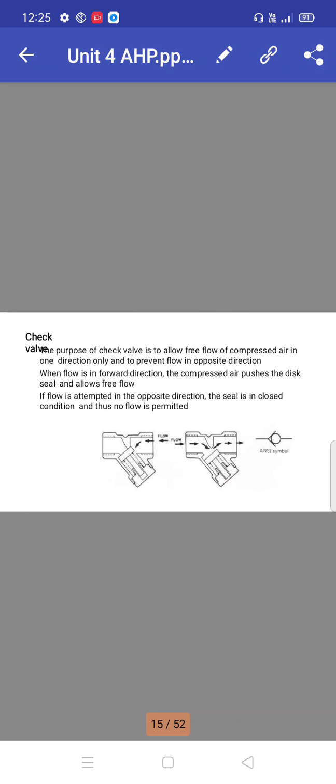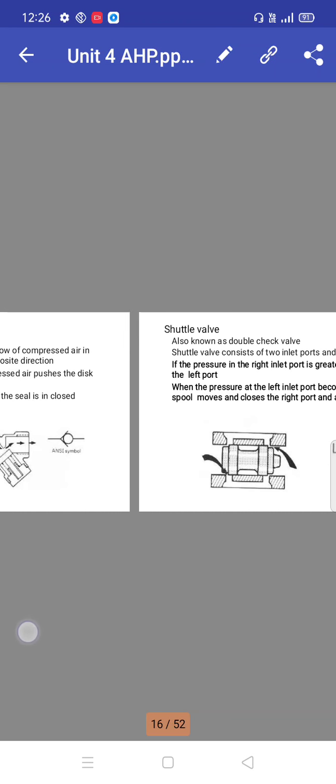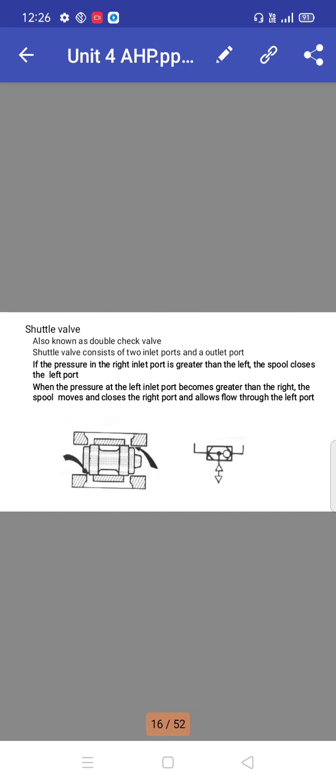Check valve: the purpose of a check valve is to allow free flow of compressed air in one direction only and to prevent flow in the opposite direction. When flow is in the forward direction, the compressed air pushes the disc seal and allows free flow. If flow is attempted in the opposite direction, the seal is in closed condition and there is no flow permitted. Shuttle valve is also known as double check valve.